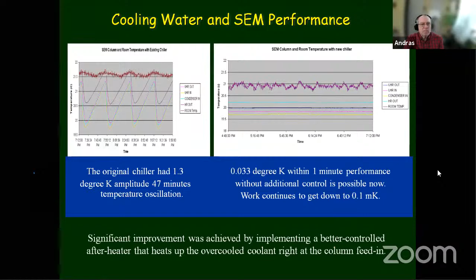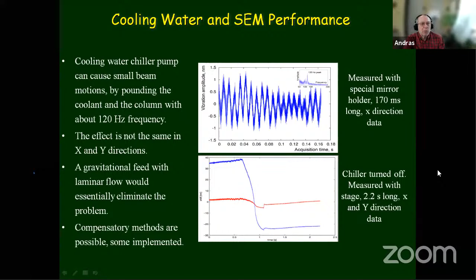So here is evidence that the chiller pump, which circulates the coolant, has or could have a significant effect on the performance of your instrument. With the laser interferometer, which one of our SEMs has, we see evidence of almost 2 nanometers' worth of wiggle that shows up in the Fourier transform at 120 hertz. This is coming from the pump, which was shaking the coolant as it was pumping the cooling water through the system. So we had to replace this, obviously, because this essentially just ruins our resolution. And we did get improvement due to that. Next slide, please.